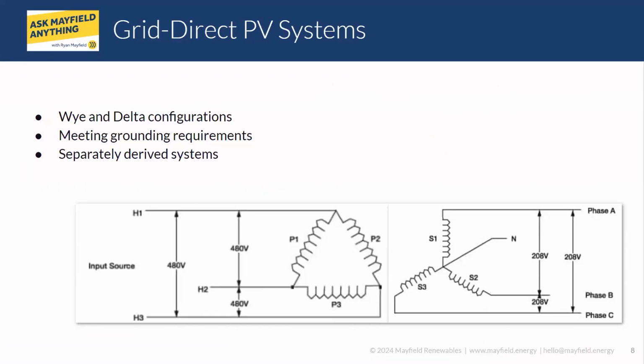So basically, there's multiple functions of an isolation transformer, but what it essentially means is that the primary and secondary have a galvanic isolation between the two. So in other words, it's not a straight electrical connection. It's actually a coupled connection magnetically. So there's some inherent things to that from a safety standpoint. An isolation transformer is a current limiting device.